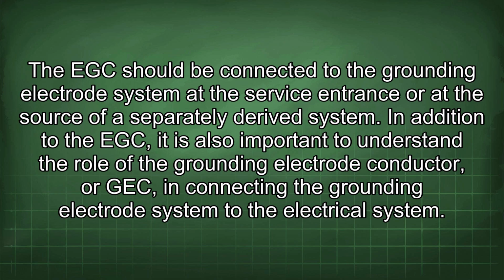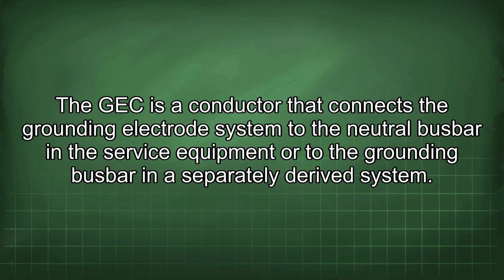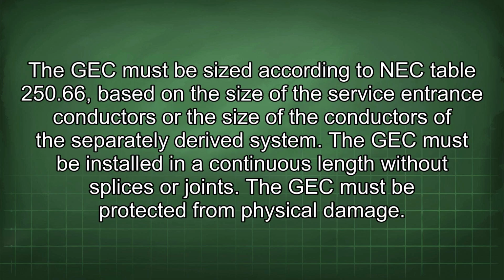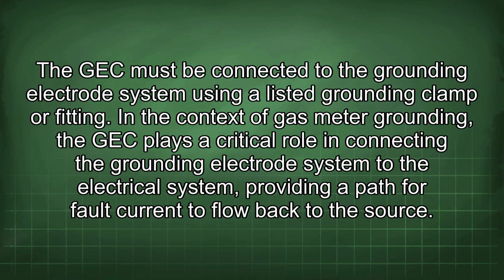derived system. In addition to the EGC, it is also important to understand the role of the grounding electrode conductor, or GEC, in connecting the grounding electrode system to the electrical system. The GEC is a conductor that connects the grounding electrode system to the neutral busbar in the service equipment or to the grounding busbar in a separately derived system. The GEC must be sized according to NEC Table 250.66, based on the size of the service entrance conductors or the size of the conductors of the separately derived system. The GEC must be installed in a continuous length without splices or joints. The GEC must be protected from physical damage. The GEC must be connected to the grounding electrode system using a listed grounding clamp or fitting.